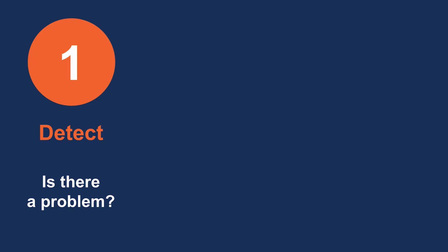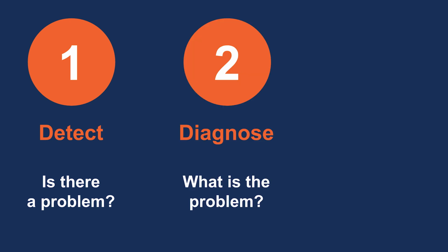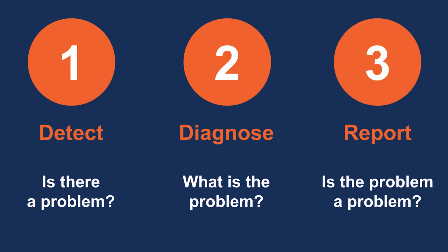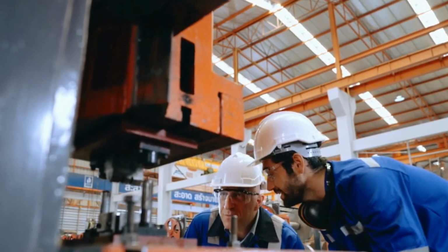Yes. So if we have a look at our frequency spectrum, let's take the 1 times. That 1 times we're going to trend over time, and then we're going to start seeing some sort of increase. Once we start seeing that increase, that's when we can say, hey, Mr. Customer, we're starting to experience some sort of unbalance on your particular equipment, and here are the actions that you should take. So vibration analysis is effectively the primary technology used on rotating or mechanical assets to see if there's something wrong. Yes.